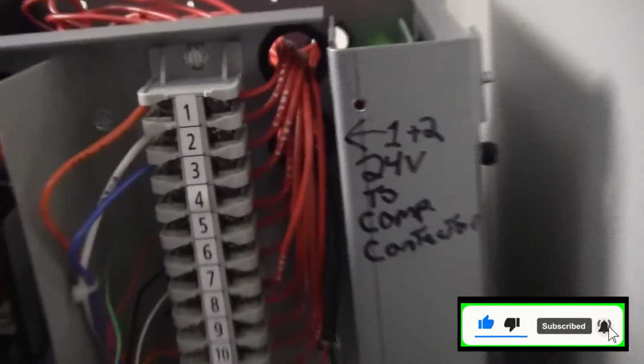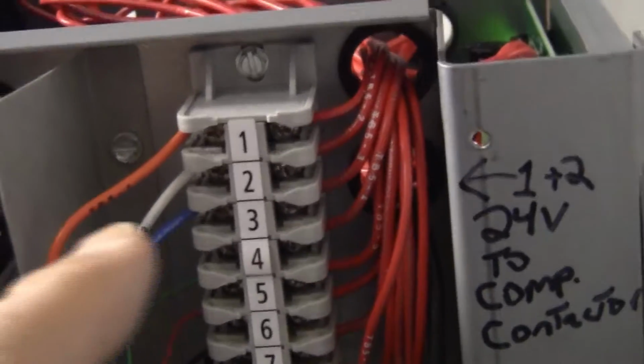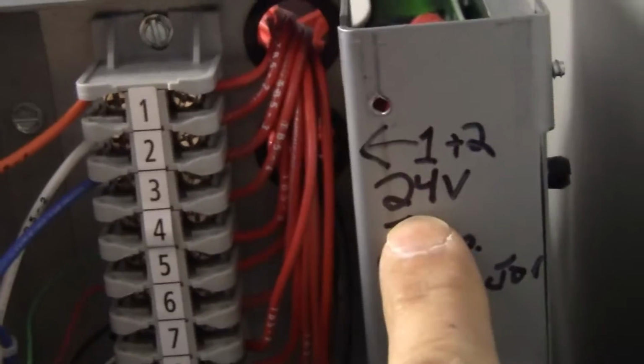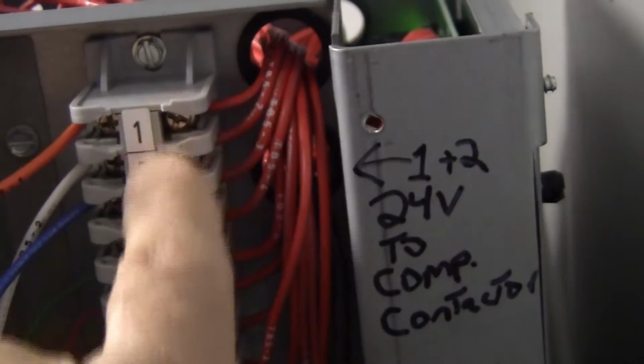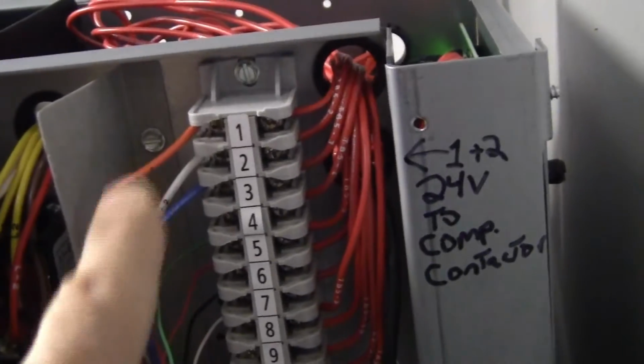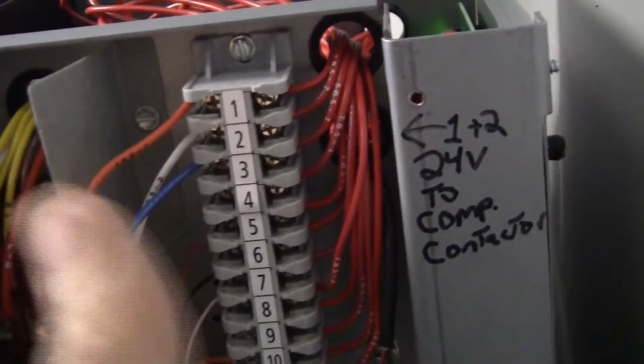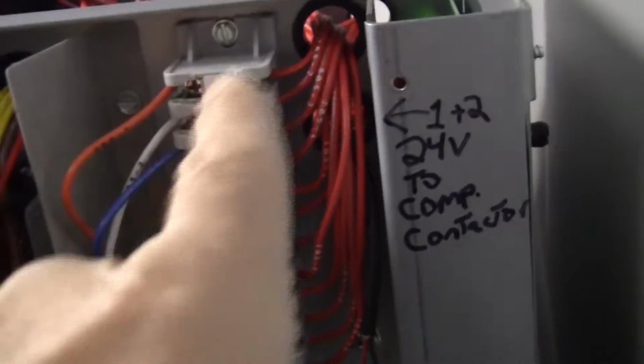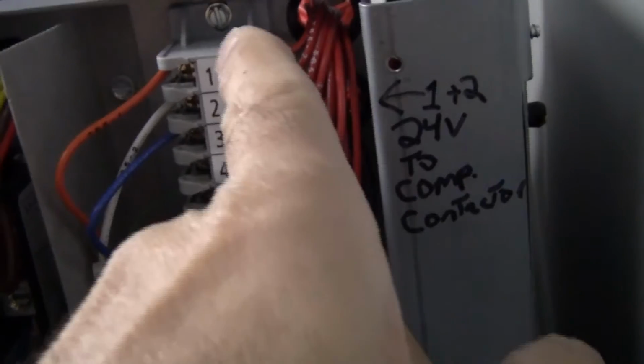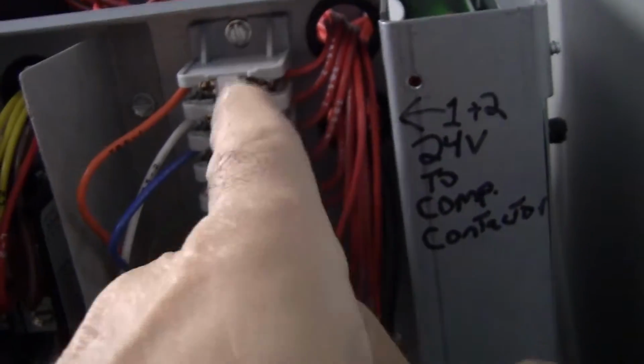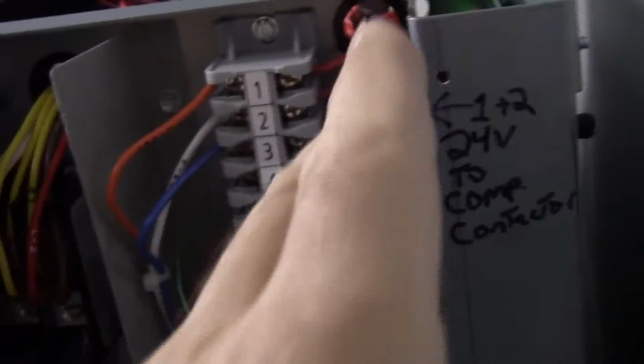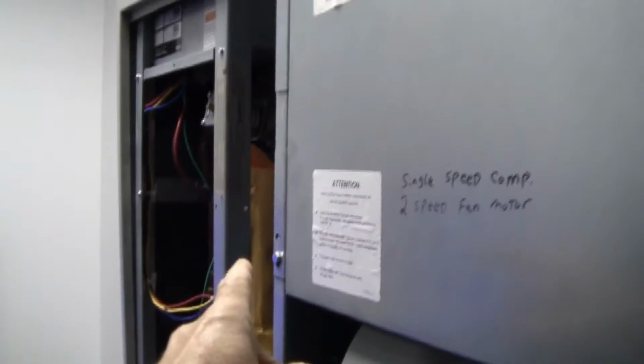I was already looking at this unit, and basically what you need over at the compressor is 24 volts on terminals 1 and 2. The white wire and the orange wire right here are the ones that go to the compressor contactor coil. I've already checked it, and there is no voltage on these two terminals. So the thermostat and the PC board are not telling the compressor to run, but the compressor is still running.